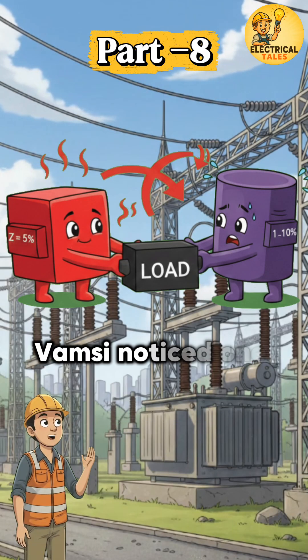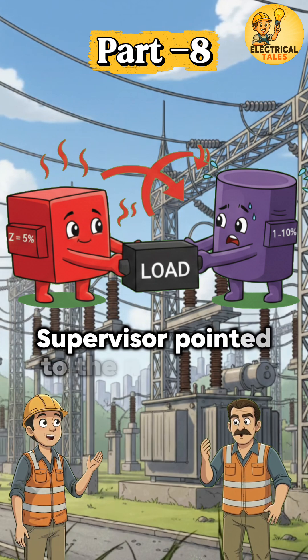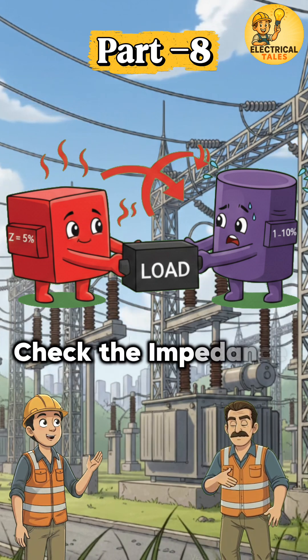While monitoring load, Vamsi noticed one transformer running hotter than the other. The supervisor pointed to the nameplate and said, check the impedance values.